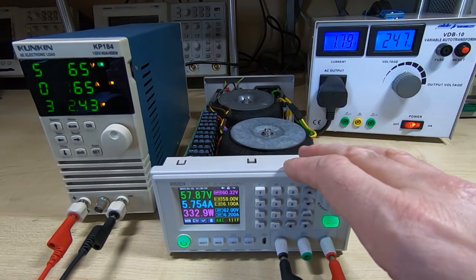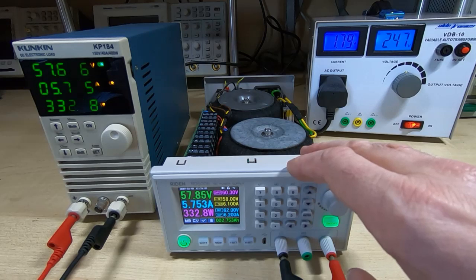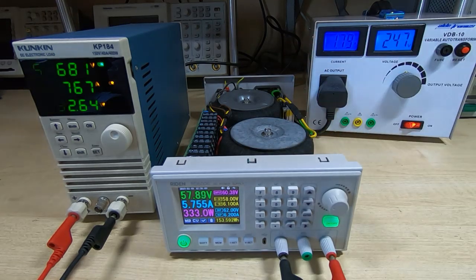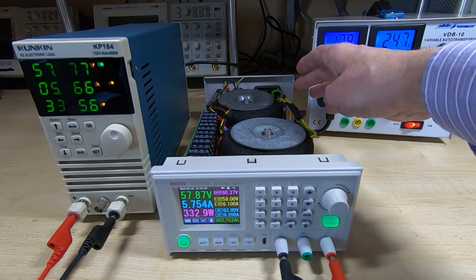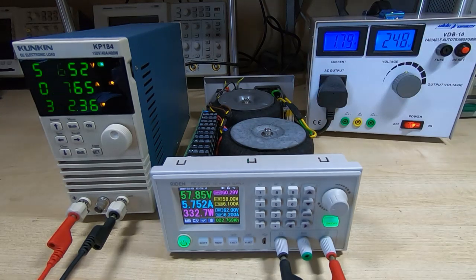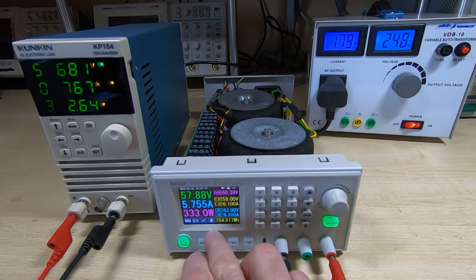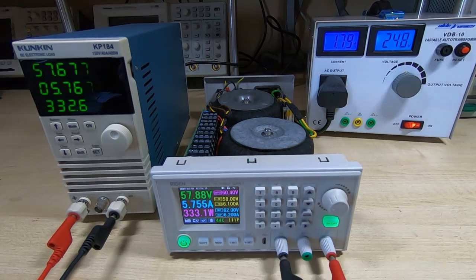This has been running with the top off. With the top on, the internals should actually be cooler than they are. So although the fan has kicked in because we're above the 40 centigrade limit, it's not really doing much, it's just sucking air in from the sides. But as you can see, the temperature is up at 44 degrees. What I'm going to do now is put the top cover on.